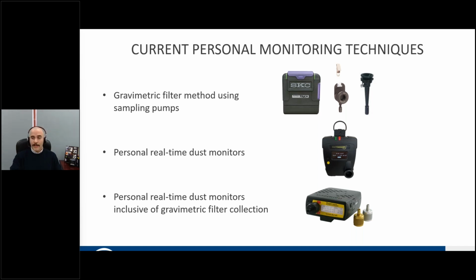So if I can see that the makeup of particles is made up of nanoparticles, because my device is telling me that 70% of that is nanoparticles on my Nanozen, then I can actually treat that risk with a finer mist or an extraction tool. So I'm able to actually understand how my controls are operating and if they're effective. So a fantastic tool from that perspective.